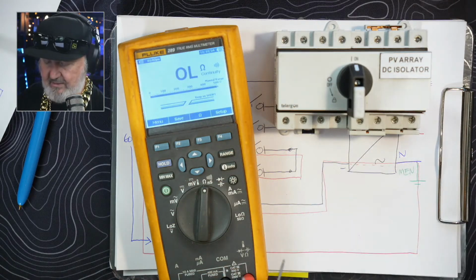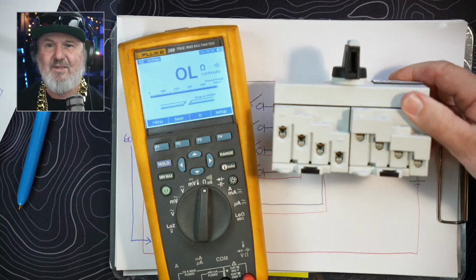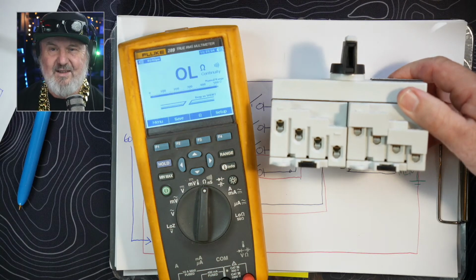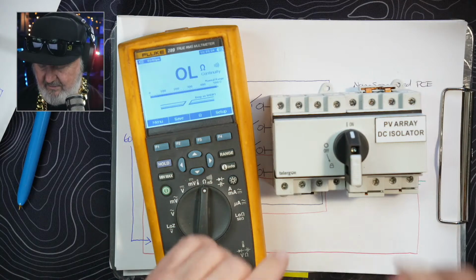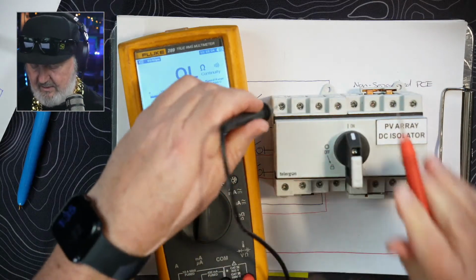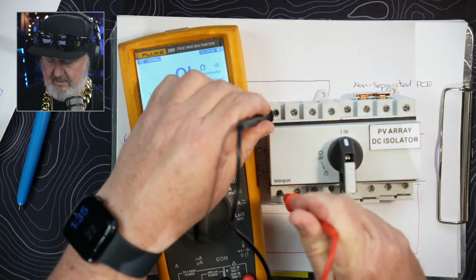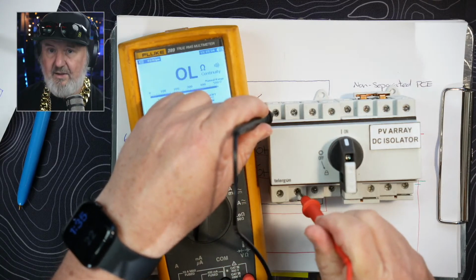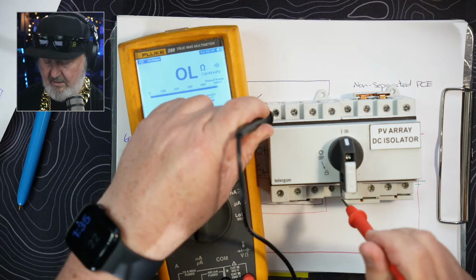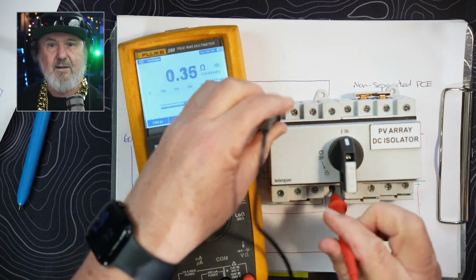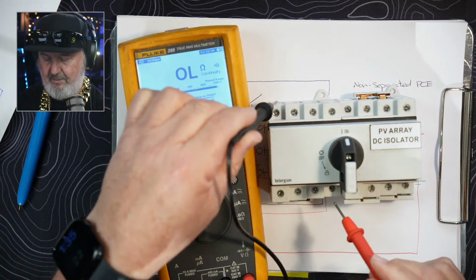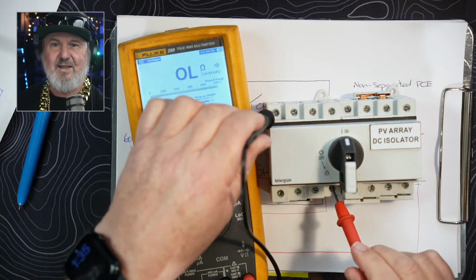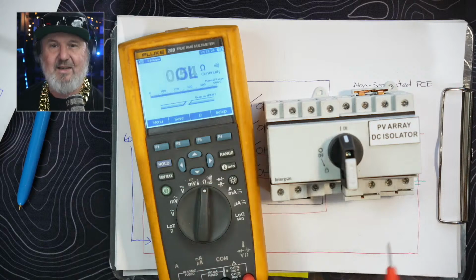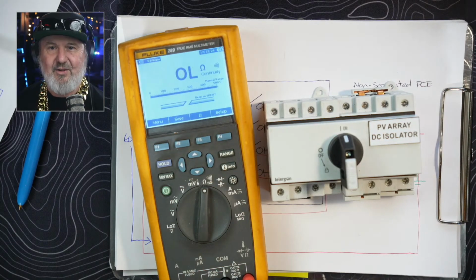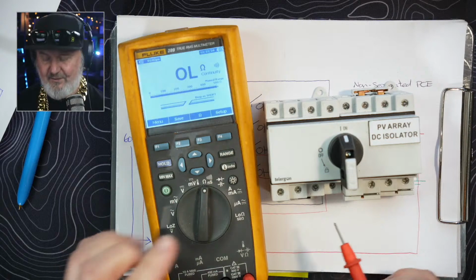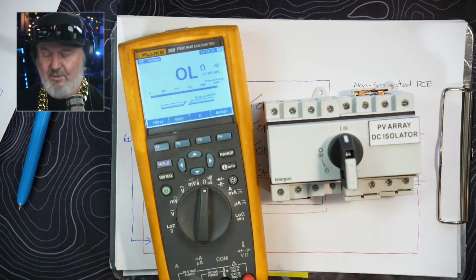But with these tiered type isolators, it's quite confusing. If I make sure it's on, yes, and nothing, nothing, nothing. Oh, look at that. So it's from top left to bottom right that is the switch. So that can really catch you out because you can accidentally wire it in a dangerous way if you think it's a pass-through. So it's good to do a continuity test.